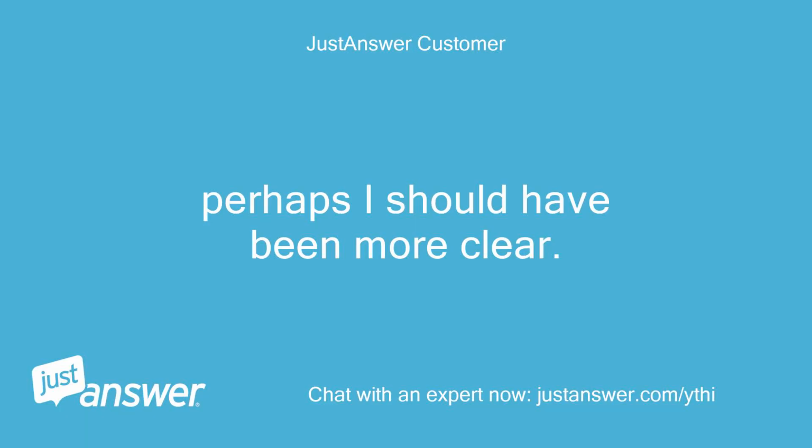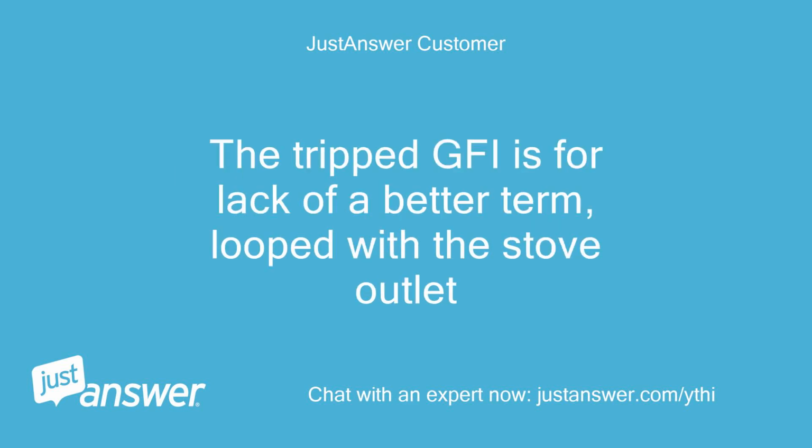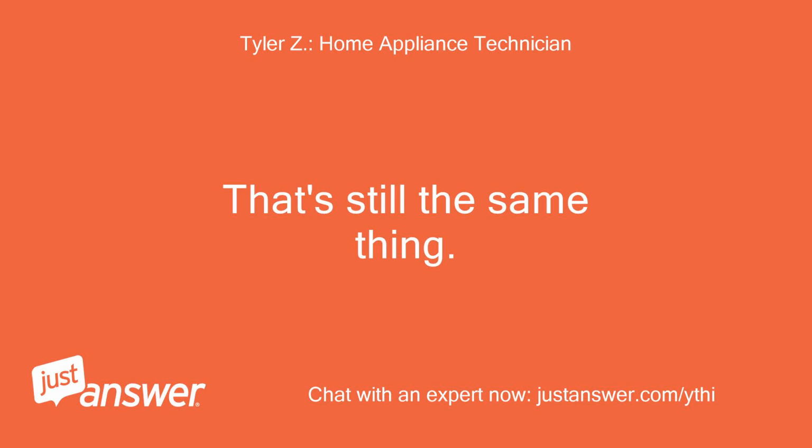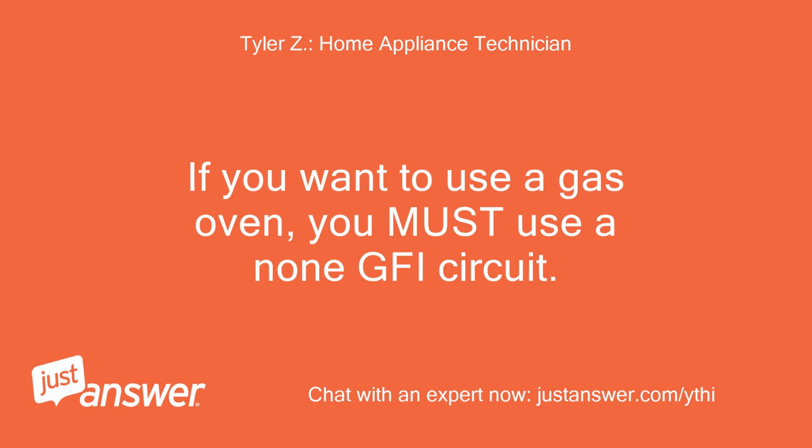Perhaps I should have been more clear. The actual receptacle the stove plugs into is not a GFI outlet. The tripping GFI is, for lack of a better term, looped with the stove outlet. That's still the same thing. If the outlet is looped in a GFI circuit, it's just like that outlet being a GFI outlet. If you want to use a gas oven, you must use a non-GFI circuit.